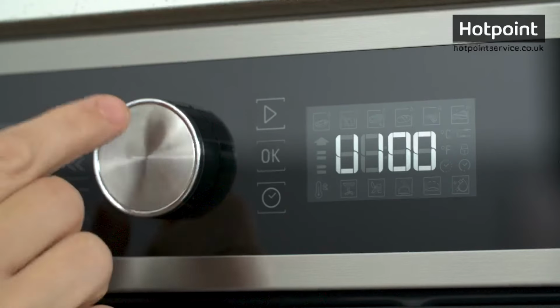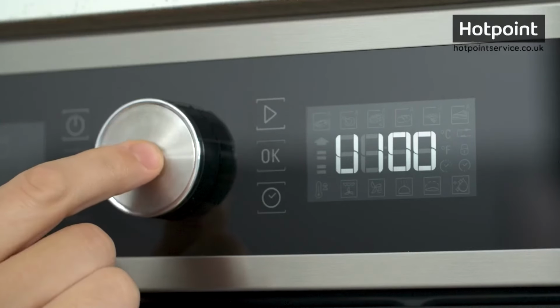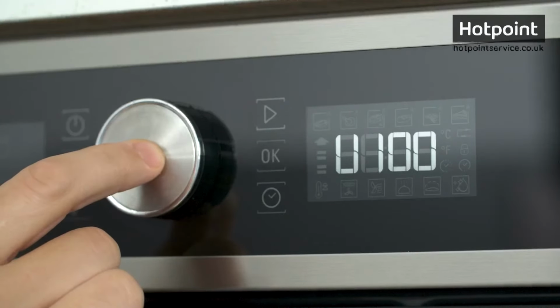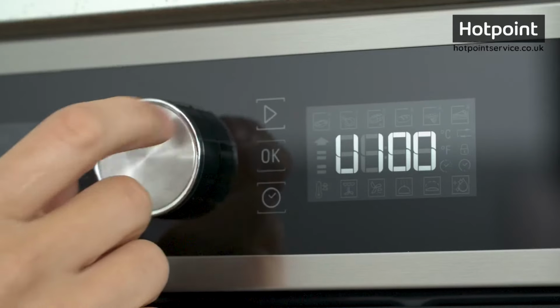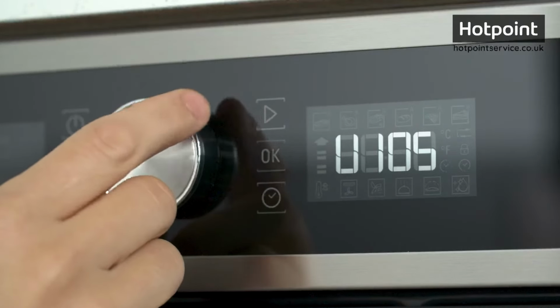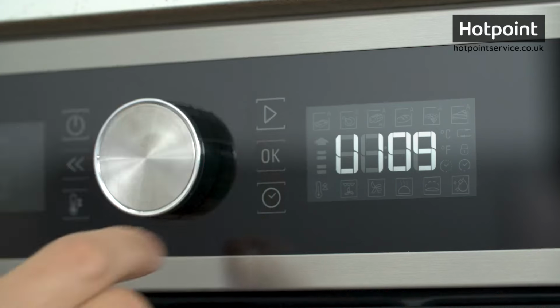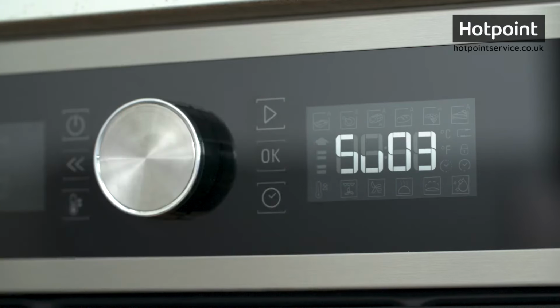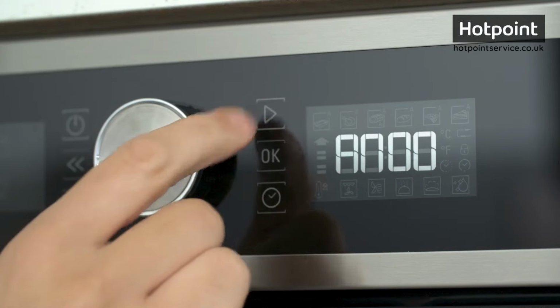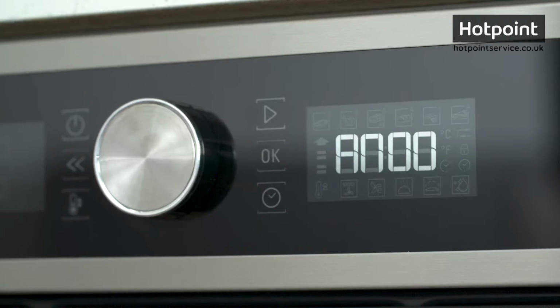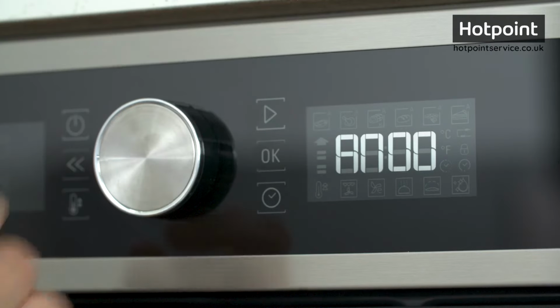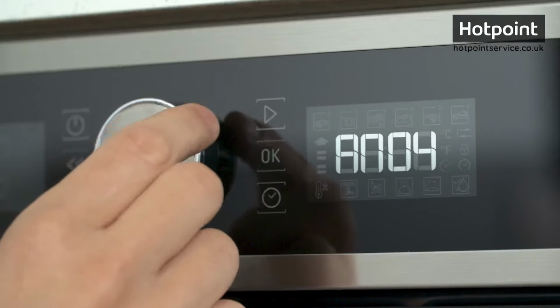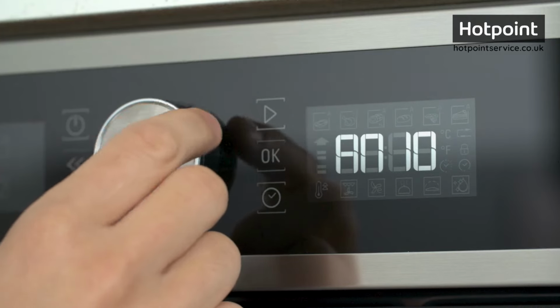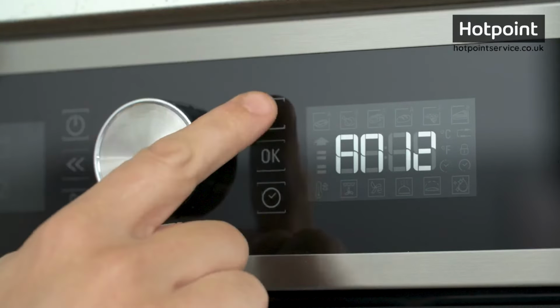00. Now use the rotary knob to select the first number from the service sticker. That was the number before the slash separator, so in our case that's 09. Like so. Then press the play key to advance. Keep advancing with the play key until an AN appears in the window. Now here's where we're going to put the second half of our code. That's the 2 digits after the slash separator, so in our case that's 12. Again, press play to confirm.